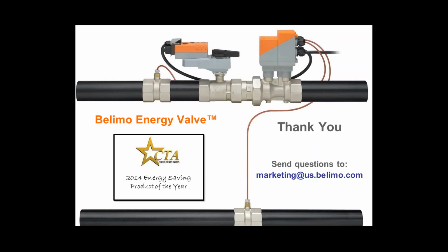If you're a data center person, it would be interesting to take a look at our upcoming webinar, which I think is actually a couple of months out. We take a break during the summer from webinars because people don't tend to show up as much, but we're going to have one on power control, which is a functionality in the Energy Valve that allows you to correlate your control signal to how many BTUs are produced at your coil. Using that in conjunction with delta T management can essentially ensure you're always producing the cooling you need in that space. So a little teaser for next time.